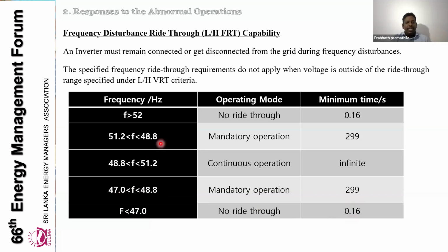Similarly, on the upper side, if the frequency is more than 52, we don't need a ride through facility, but up to 160 milliseconds the inverter shall remain connected. From 48.8 to 51.2 Hz, the inverter needs to be connected to the network and should provide support to ride through.